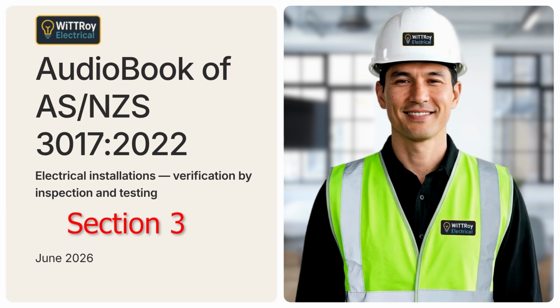Clause 3.2 Safety Requirements before visual inspection. Clause 3.2 explains the safety requirements before visual inspection starts. Before carrying out the inspection, a risk assessment must be done. The purpose of the risk assessment is to identify hazards and risks. It also helps decide what controls are needed before the inspection starts. The risk assessment should identify whether suitable PPE is needed. PPE means personal protective equipment. For example, depending on the site, this may include safety glasses, gloves, protective clothing, safety footwear, or other required protection.